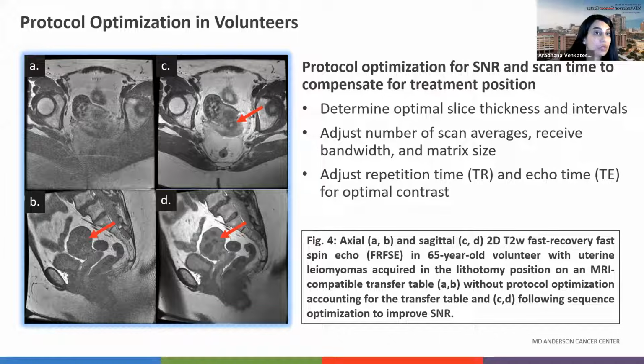You're also able to confirm whether the slice thickness prescribed in your protocol is in fact optimal for your needs to visualize adequately the tumor and your hardware, including any slice thickness intervals should you choose to build those in. Most of our sequences for our 3 Tesla protocol that are high resolution sequences are 2 millimeters without a gap. If you're using an older scanner or 1.5T scanner, you may need to adjust that slice thickness, i.e. typically increase it to say 3 millimeters, given you're going to expect a reduction in SNR. And the thicker slices will reduce the relative noise at the lower field strength that you will encounter.